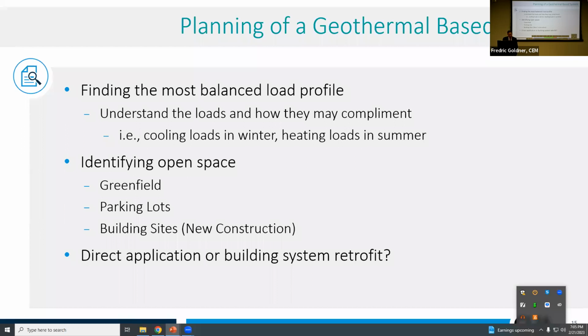We can inject off of the high temperature loop into the geo loop across heat exchangers. Same thing for the campus's existing cooling towers—we can keep them online until we've proven the system works or we've taken on more scale so we don't need to reject that heat. So the adaptability of an existing building to be retrofitted into geo, it's there. And if anyone wants to argue otherwise, just listen, and hopefully you'll learn something, because I've seen that it's very, very easy.